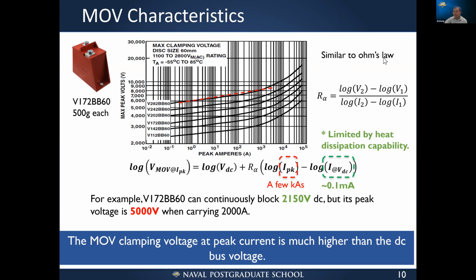So we can define this, similar to Ohm's law. We can define a kind of resistor, right? It's a ratio between delta V over delta I in the log scale. This is also the recommended model from the vendor. And then we can estimate the voltage at peak current, which equals the system DC voltage plus the voltage increase due to the current increase, from once the voltage crosses only 2 kilovolts to when the current is a few kiloamps, the peak current.